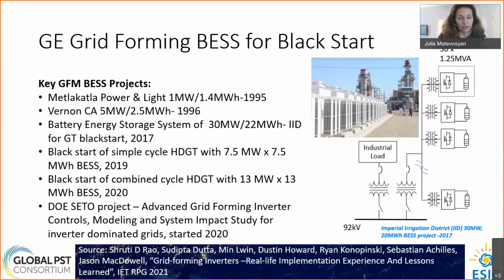The rest of the projects on the list are black start applications. So this is where a grid forming battery is being used to power up auxiliaries on heavy duty gas turbines. So basically those gas turbines can be started without being connected to the grid or any other synchronous generation in the vicinity. Once the auxiliaries are powered up, that turns the gas turbine into a black start unit, and it can provide black start capability for the rest of the grid. So what's done in this project, the battery is added to the gas turbine. There is very little modification needed to the original plant. And soft start is used in the grid forming battery to gradually increase voltage, and this way limit inrush currents at the motor start and transformer energization.